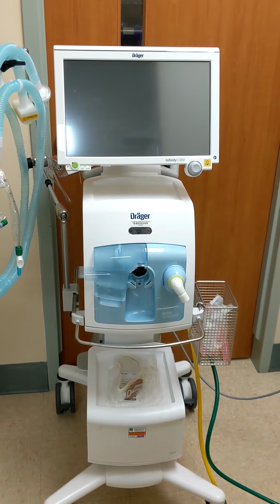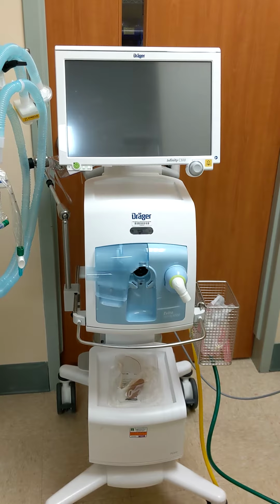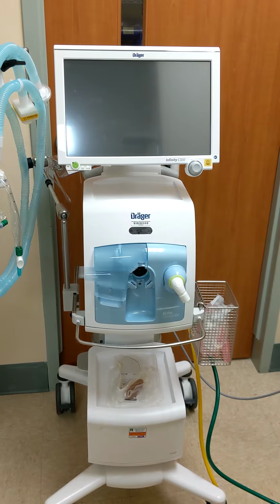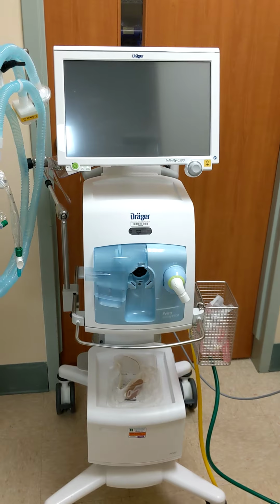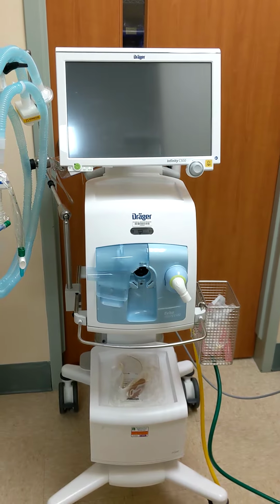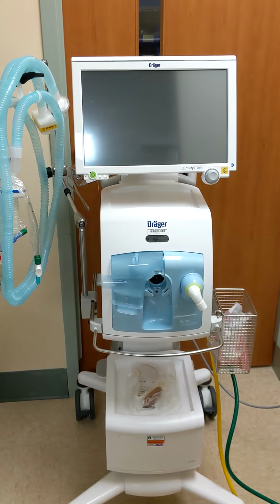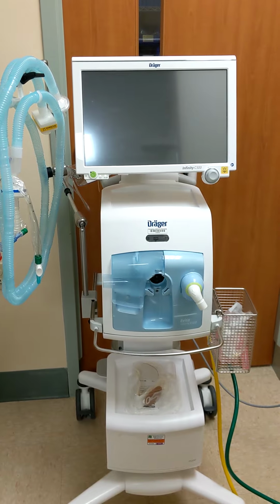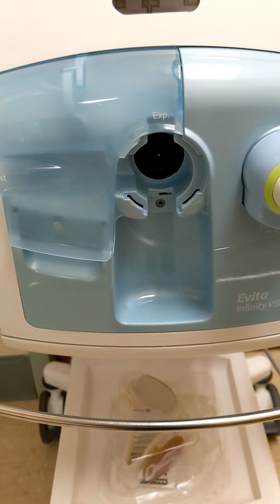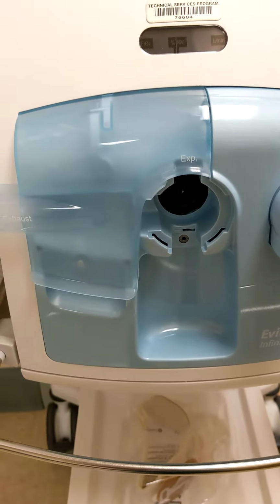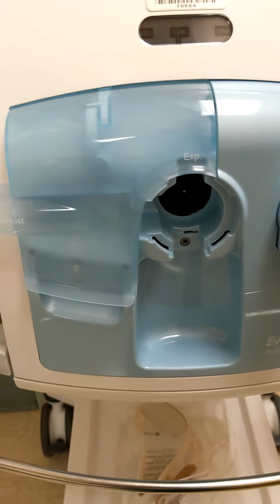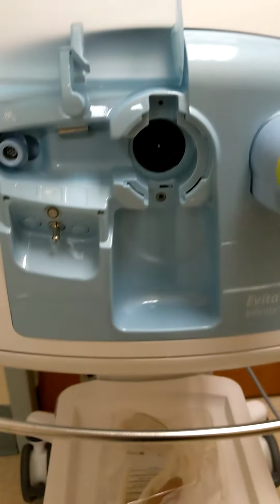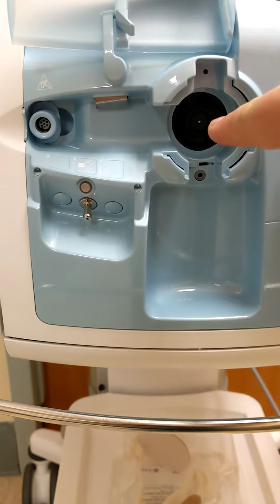In this video we will show you the proper setup for the expiratory valve, flow sensor, vent circuit, and the QC that you must go through when you reset a vent. On the front of the vent, you will see this area here. You flip it up. This is where the expiratory valve goes, and this is where your flow sensor goes.